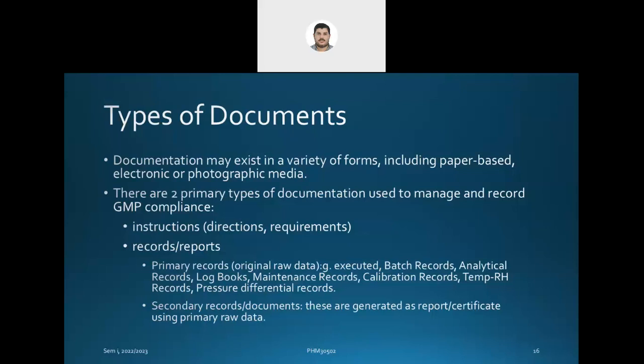The records or reports are like primary records, original raw data. Examples: the executed batch record, analytical records, logbooks. They have the original data. Maintenance records, calibration records, temperature, humidity records, pressure differential records.